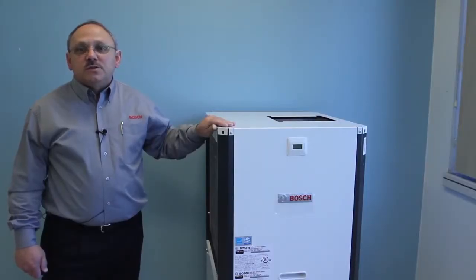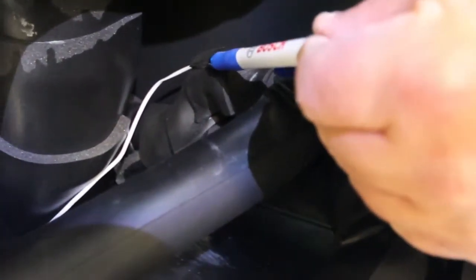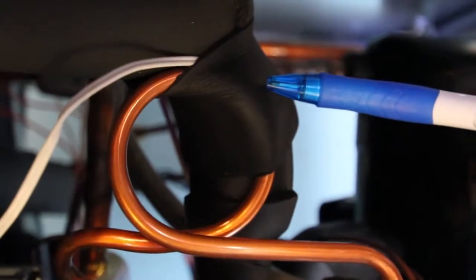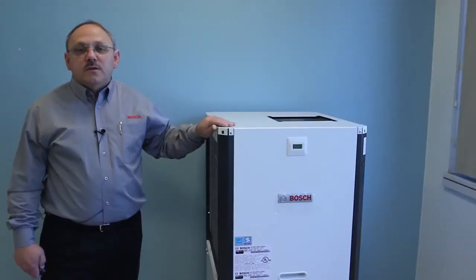The water coil sensor is located on the refrigerant line between the TXV and the water coil. The air coil sensor is located on the refrigerant line between the air coil and the thermal expansion valve. Both are set at a default temperature lockout of 30 degrees.